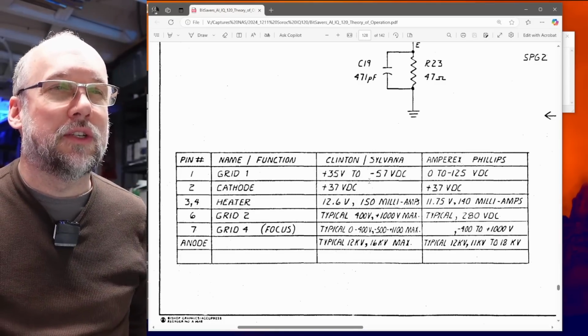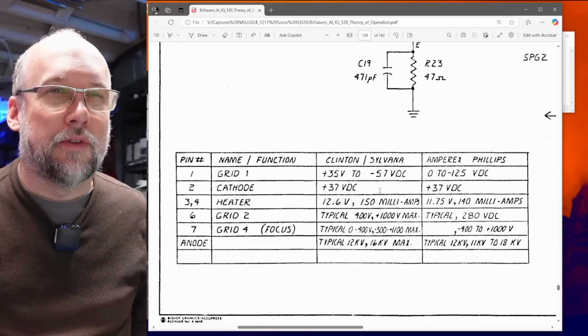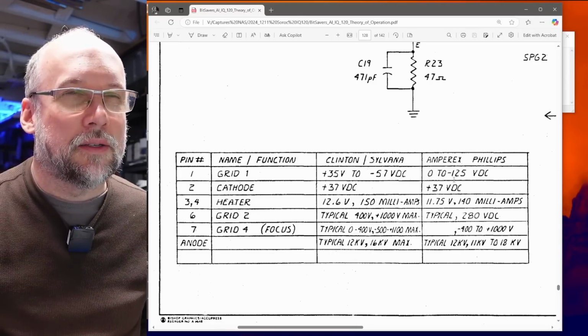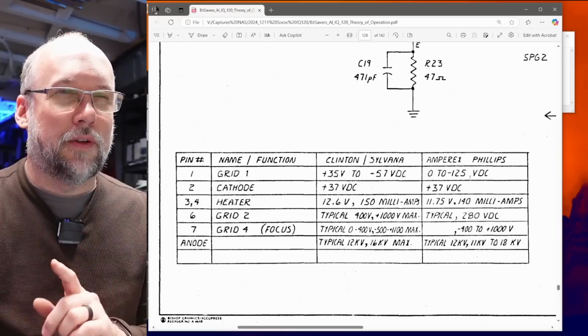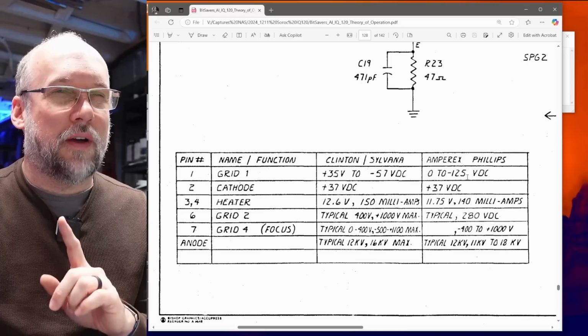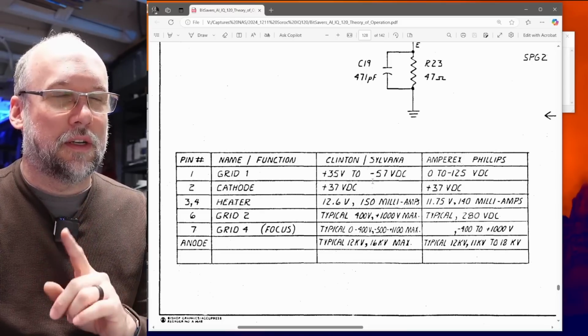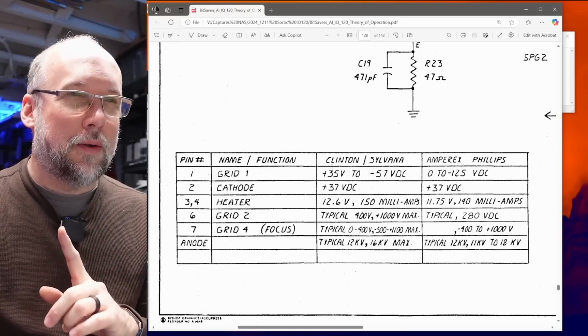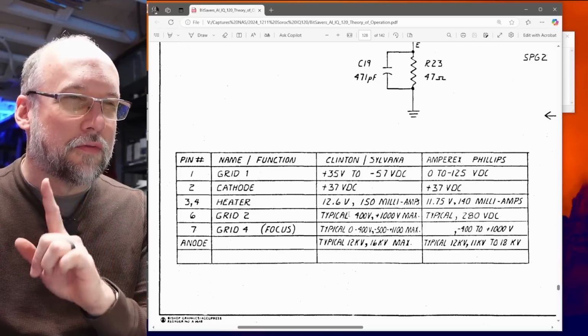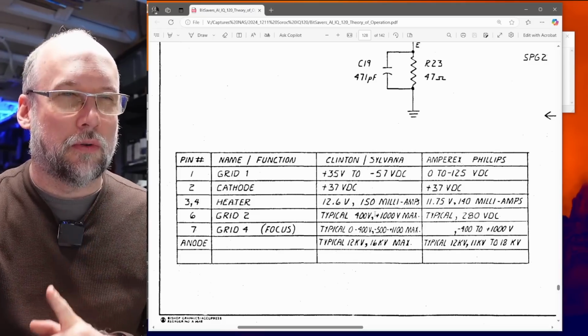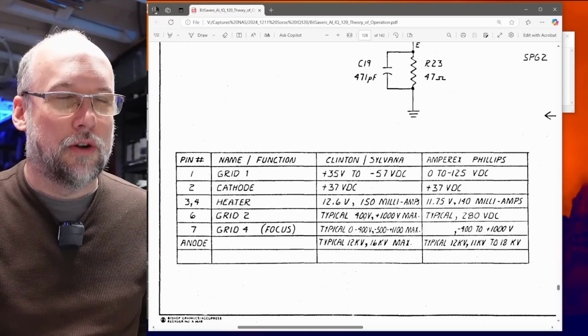The grid 1 voltage, which is the brightness control, is a little different too — 0 to minus 125 volts on the Philips, and plus 35 to minus 57 volts on the Clinton. I think we can get away with it not being exactly right if the grid 2 voltage was more correct, around this plus 400 volts.